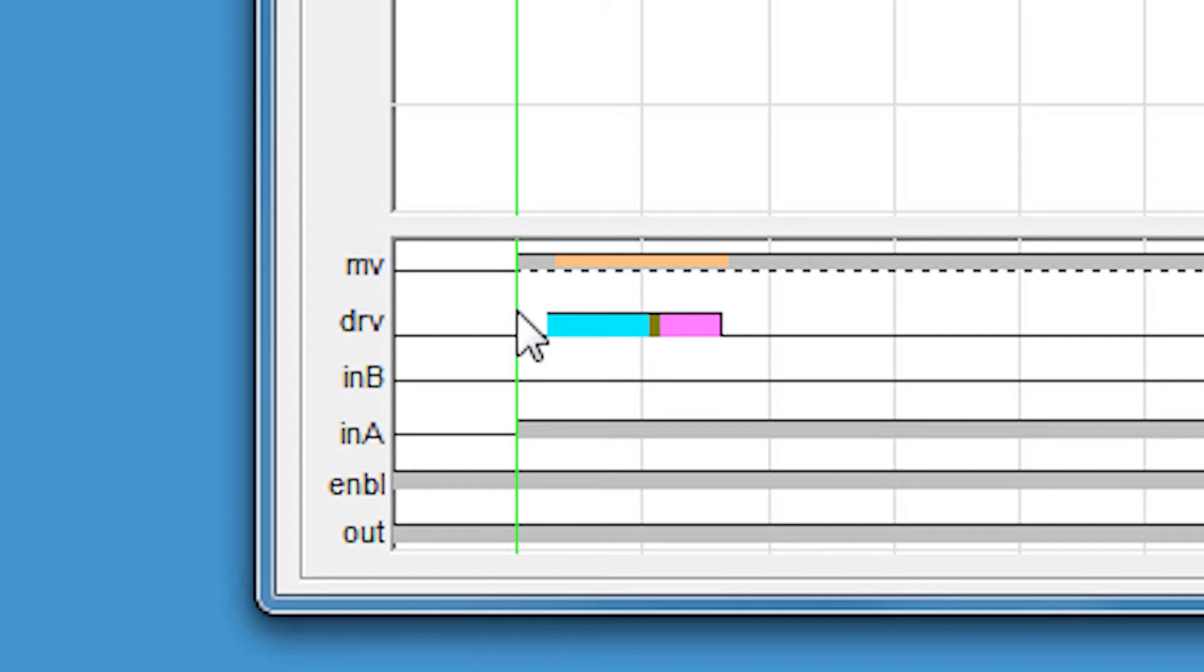After the blue color, you'll notice there's a small olive green section. That olive green represents voltage saturation and torque saturation at the same time. Voltage saturation is analogous to torque saturation, where there's just not enough voltage from a power supply to adequately reach your move spec. This message is very helpful in identifying potential power supply limitations. In some applications, customers might run off a lower voltage supply. You'll get the most power out of a ClearPath at 75 volts DC, but at lower voltages, your top speed may be limited by the power supply.